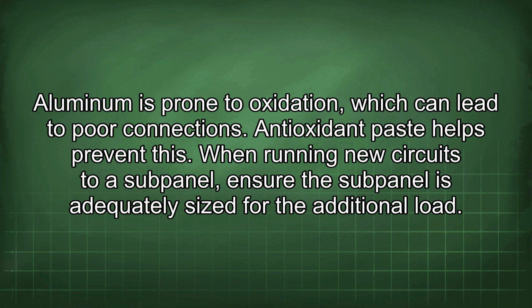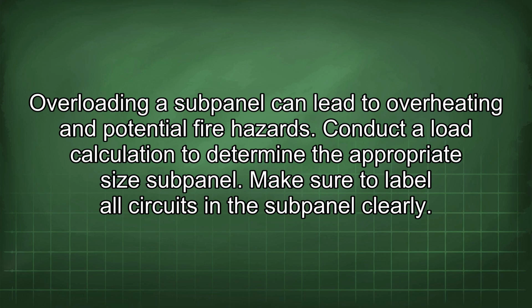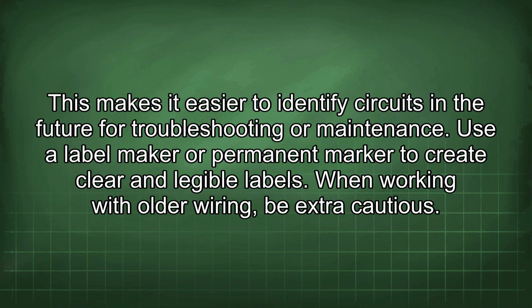When running new circuits to a subpanel, ensure the subpanel is adequately sized for the additional load. Overloading a subpanel can lead to overheating and potential fire hazards. Conduct a load calculation to determine the appropriate size subpanel. Make sure to label all circuits in the subpanel clearly. This makes it easier to identify circuits in the future for troubleshooting or maintenance. Use a label maker or permanent marker to create clear and legible labels.